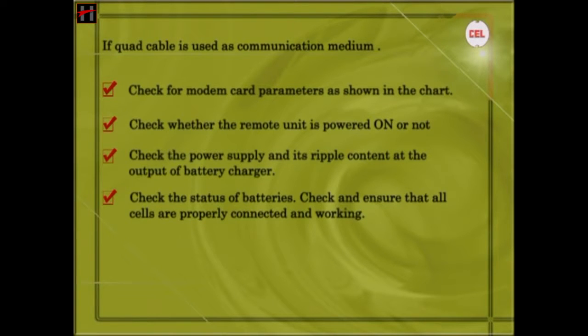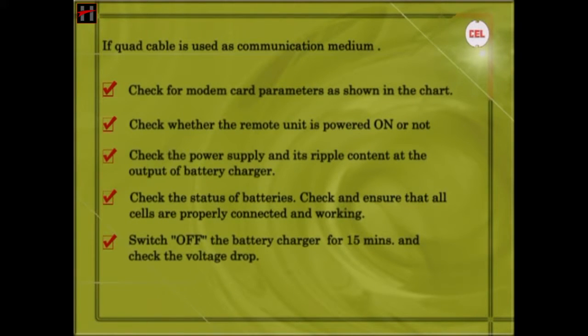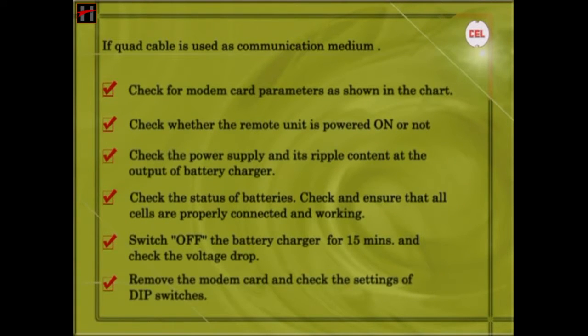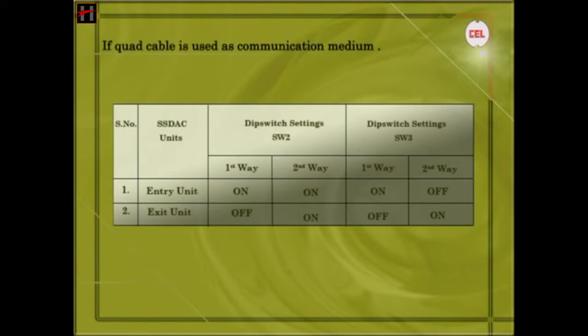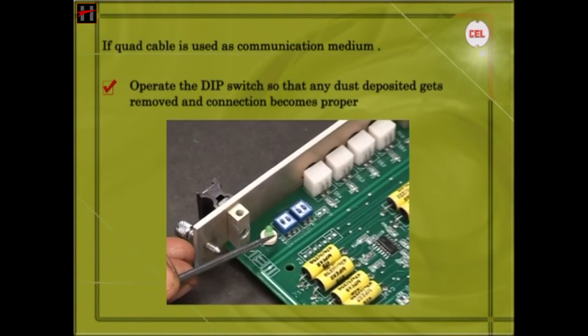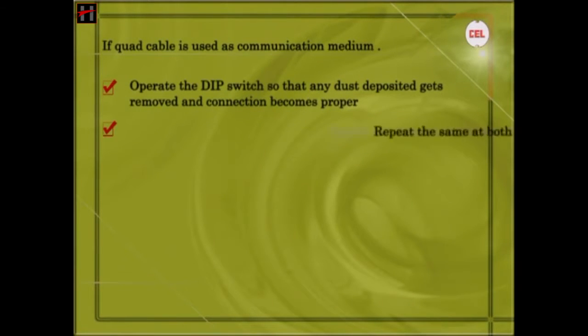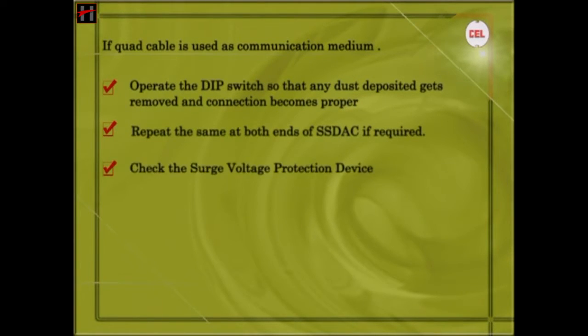Check the status of the batteries and ensure that all the cells are properly connected and working. Switch off the battery charger for 15 minutes and check the voltage drop. Remove the modem card and check the settings of the DIP switches. Operate the DIP switch so that any dust deposited may be removed and the connection becomes proper. Repeat the same at both ends of the SSD AC if required.